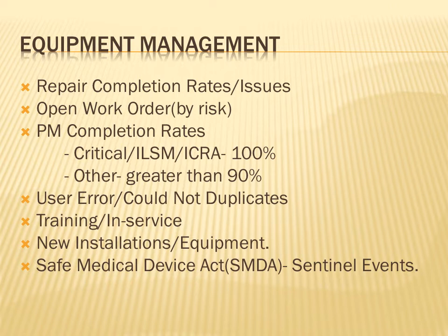And again, understand that the SMDA sentinel event is a very specific document with a very specific process that needs to be filled out and sent in. It's been some years since I filled one out, but I used to fill them out. I probably filled out maybe a half dozen of them or so over my career for events that have occurred, and nothing where anyone died, but where people were injured. So it's a document you want to get some familiarity with. It's fairly straightforward, but you'll be working with your risk managers and your quality folks when that happens. So these are just some examples of equipment information that needs to be reported.